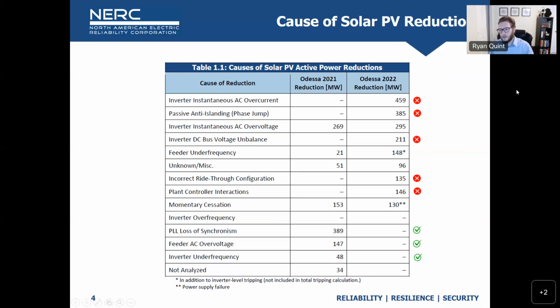So the OEM, and it's documented in the disturbance report pretty well, has gone through and developed mitigations for most of these new issues too, and now it's a matter of rolling those out to the fleet at large. That's the work going on right now. The other example I'd highlight is that we added some asterisks this time to differentiate: if you add up this column, it doesn't add up to 1711, the total resource loss, it adds up to a larger amount, because in many cases the inverters all trip but then feeder level protection also trips. So if you're just fixing the feeder level protection issue, you're maybe not fixing the inverter level issue, and the next event it's just going to trip again. I highlight both of those as examples.